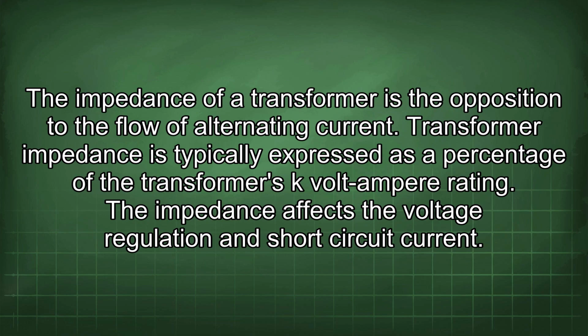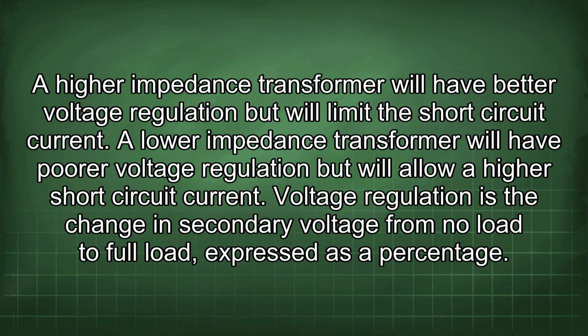The impedance of a transformer is the opposition to the flow of alternating current. Transformer impedance is typically expressed as a percentage of the transformer's kV-ampere rating. The impedance affects the voltage regulation and short-circuit current. A higher impedance transformer will have better voltage regulation but will limit the short-circuit current. A lower impedance transformer will have poorer voltage regulation but will allow a higher short-circuit current.